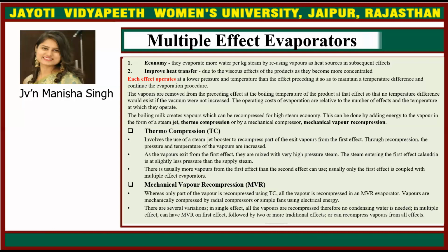Then the second kind is mechanical vapor recompression. Whereas only part of the vapor is recompressed using thermocompression, all the vapor is recompressed in mechanical vapor recompression evaporators. Vapors are mechanically compressed by radial compressors or simple fans using electrical energy. There are several variations. In single effect, all the vapors are recompressed, therefore no condensing water is needed. In multiple effect, we can have mechanical vapor recompression on the first effect, followed by two or more traditional effects, or we can recompress vapors from all effects.